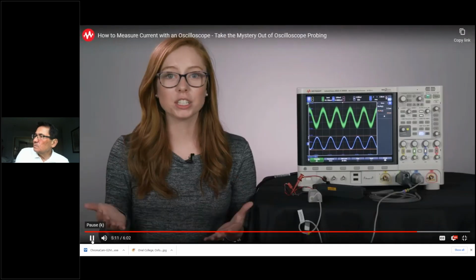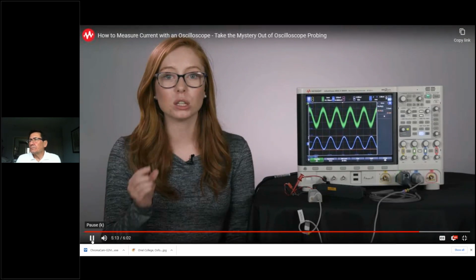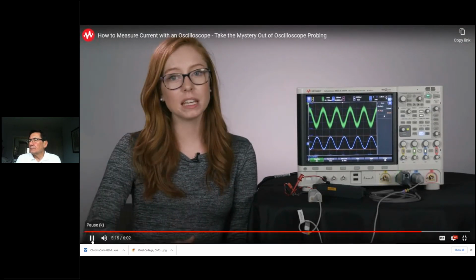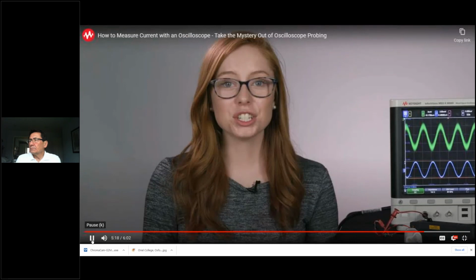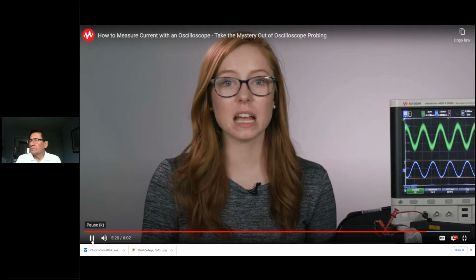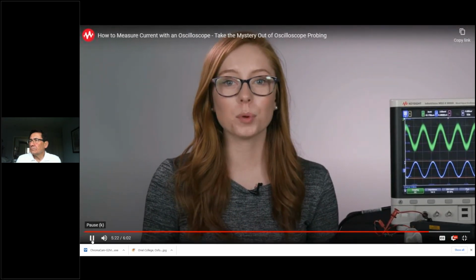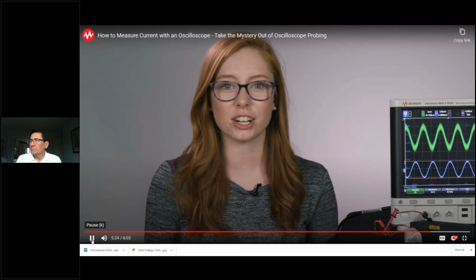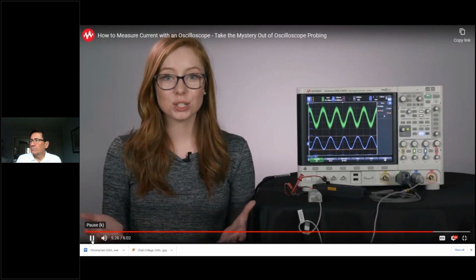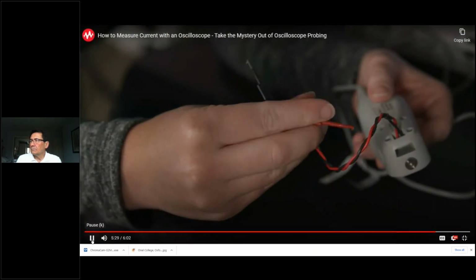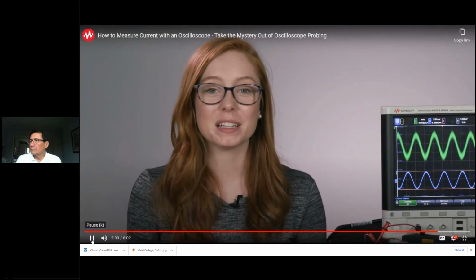And often when you're doing current testing, you need to be able to make low-level current measurements while still being able to analyze those larger currents. And to do this, you have two options. First, you can double probe your signal, but this will double probe loading and give you an inaccurate view of your signal. The other option is to use a two-channel high-sensitivity current probe like this one. Making more accurate current measurements starts with the right probe.